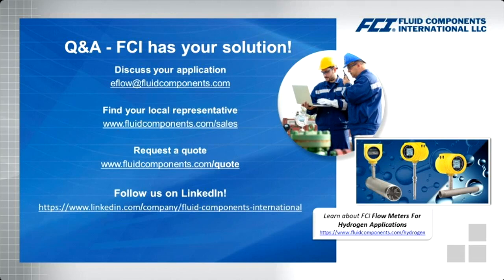Right. Next one here, Brian. Do thermal mass flow meters have minimum piping requirements? Absolutely. Like most flow technologies, there are minimum requirements that we have. Ideally, at the factory, we calibrate in what we call the perfect flow stream. So it's 20 diameters up and 10 diameters down. That's our recommendations. Different manufacturers have different recommendations.